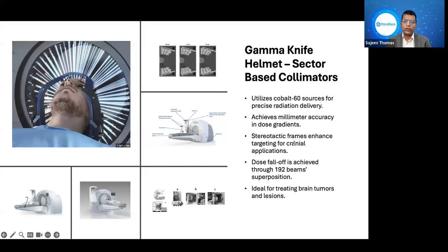So the new Gamma Knife systems use sector-based dynamic collimators, whereas the old systems used fixed collimators. So the sources are grouped into 8 sectors that open and close independently for beam shaping and efficient delivery without manual intervention. And for the patient positioning system, the initial systems used a traditional frame-based approach, and the most modern systems like Elite, Spirit, Perfexion have the option to do frameless radiosurgery using frameless mask-based systems, including a robotic couch movement and with submillimetric accuracy.